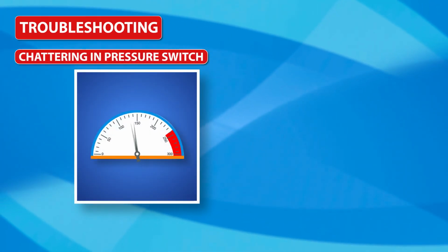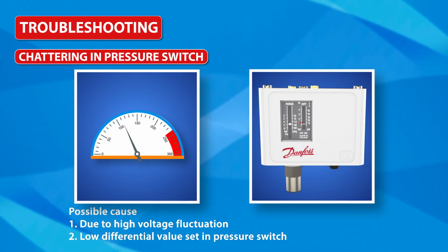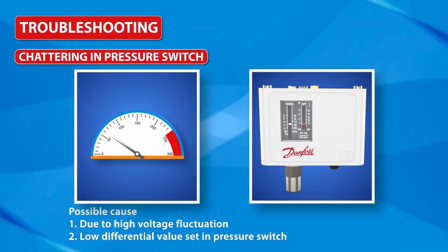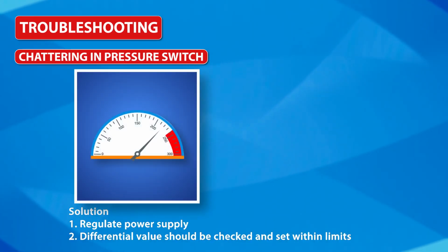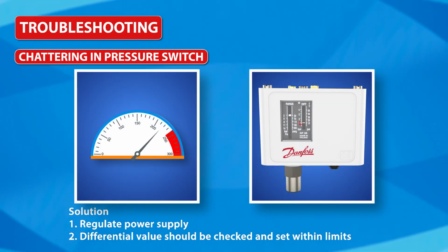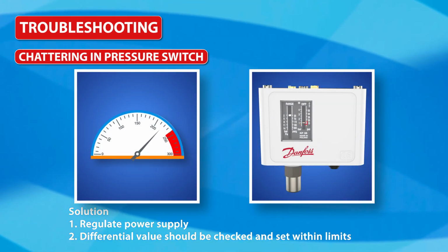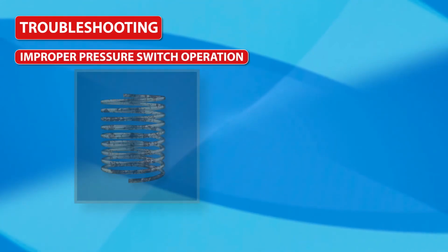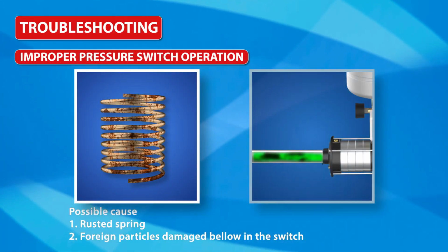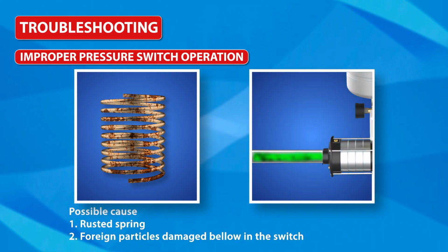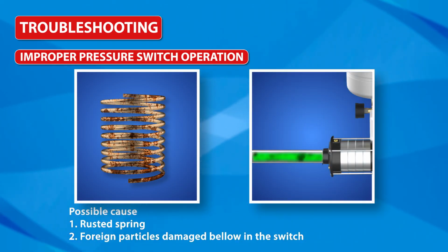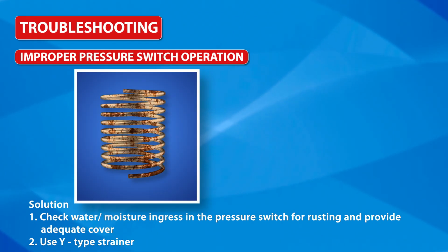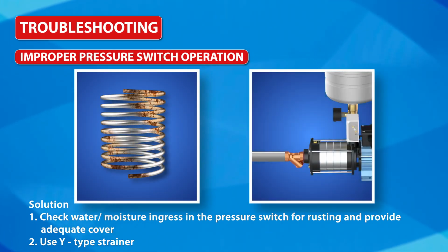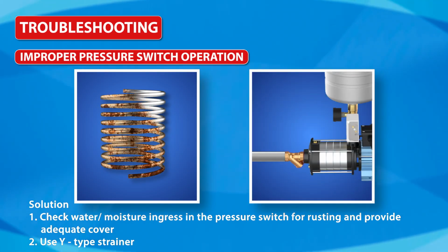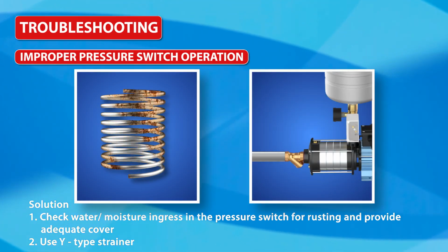Chattering in pressure switch. Possible cause: first, high voltage fluctuation. Second, low differential value set in the pressure switch. Solution: first, regulate power supply. Second, differential value should be checked and set within limits. Improper pressure switch operation. Possible cause: first, rusted spring. Second, foreign particles damaged the bellow in the switch. Solution: first, check water or moisture ingress in the pressure switch for rusting and provide adequate cover. Second, use a Y-type strainer.